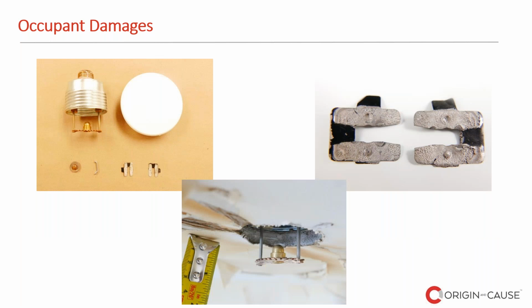Again, as I was saying, in other cases, when you have the fusible link, it's important to collect all the parts. In this case, we have most of the parts, and then we can look very closely at those features in the fusible link and determine whether there was some heat applied, like with a torch or something like a hair dryer, or simply it was a manufacturing defect or some material issue which caused it to creep. And then we can differentiate whether the failure was due to a manufacturing issue or as a result of damage by the occupant, or intentionally damaged.